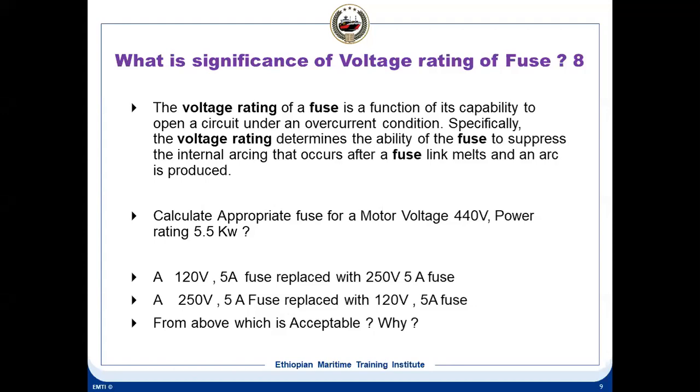It will be 5500 watt divided by √3 into 440 into power factor, multiplied by 1.25. That will give you the value of the fuse.